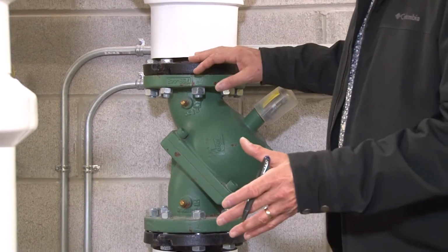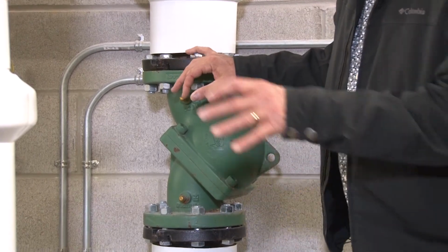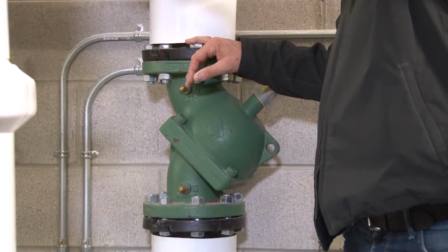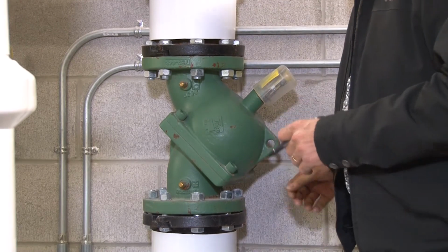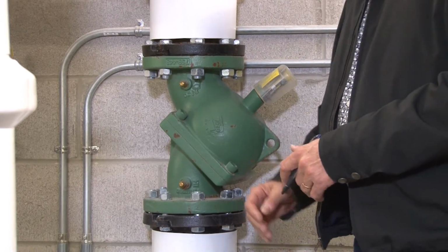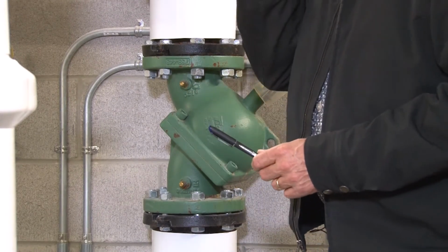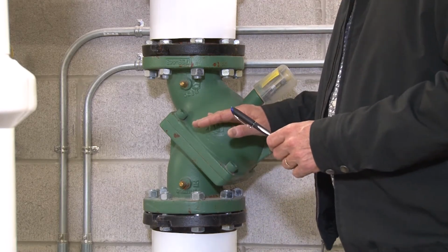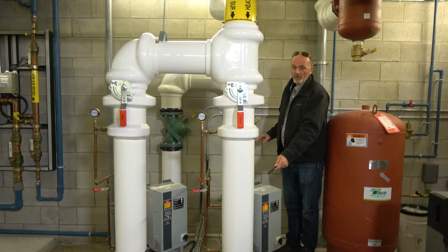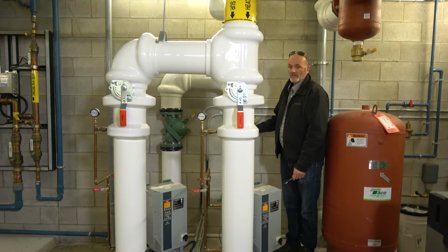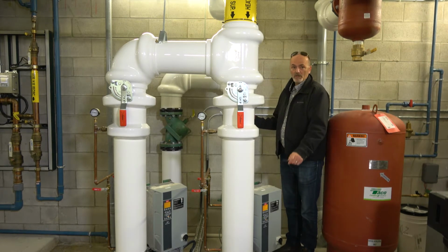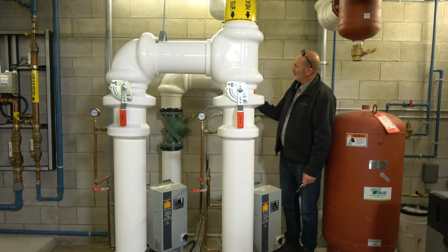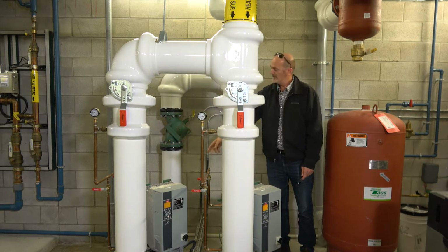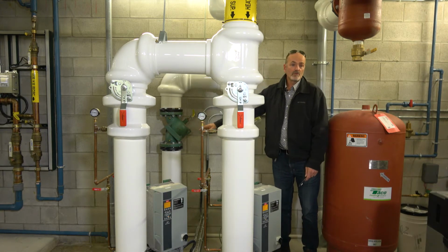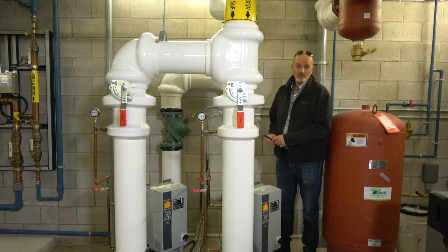So on every one of the vertical inline pumps on the job, for both these two heating and the two chilled water over there, there's also a multi-purpose valve. It performs a few functions. One, it's a check valve. So if this pump's running, the check valve will swing open because we have flow, but rather than push it back into this pump, which is off, there's a check valve that won't allow reverse flow, so all the flow goes out to the system.